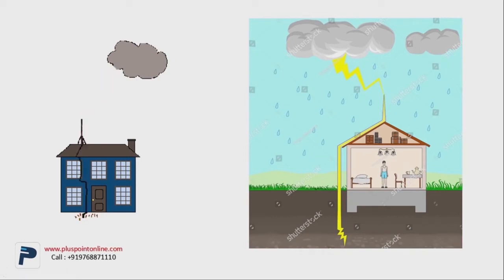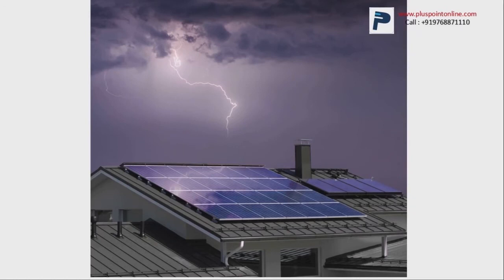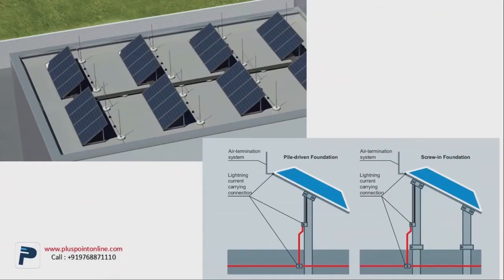Hence, this system is quite popular and is extremely effective on huge buildings. Along with this, it has proven to be more than adequate on the solar panels as well. If you have installed solar panels on the roof of your buildings, that also needs protection from the lightning strikes. This system is also installed next to the solar panels. Either by having the lightning rod or the copper rod, one can create the lightning protection system.